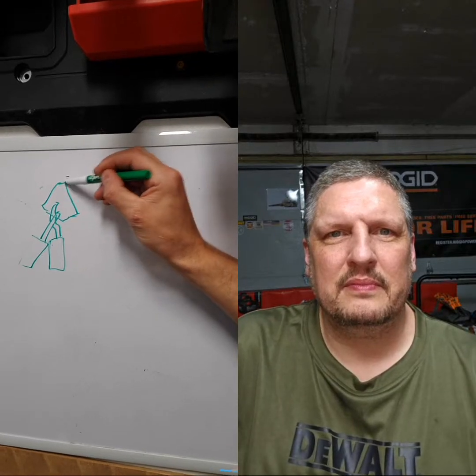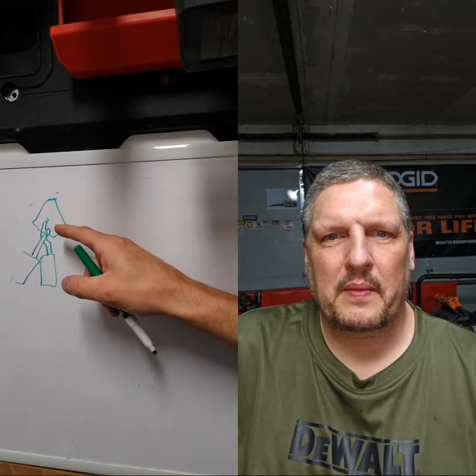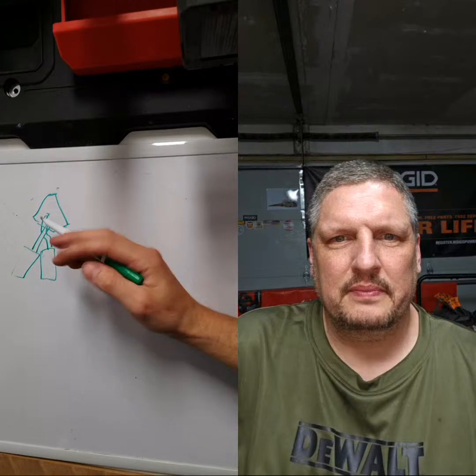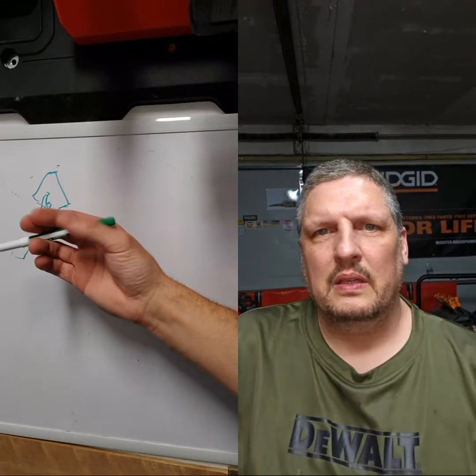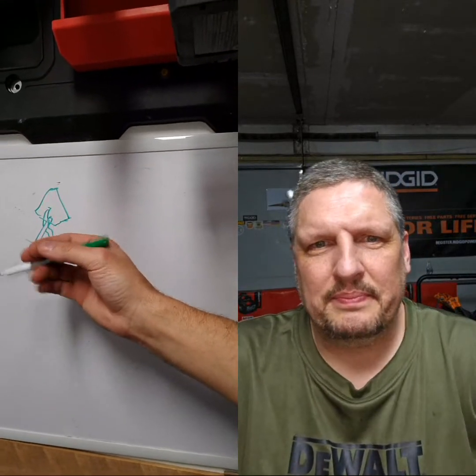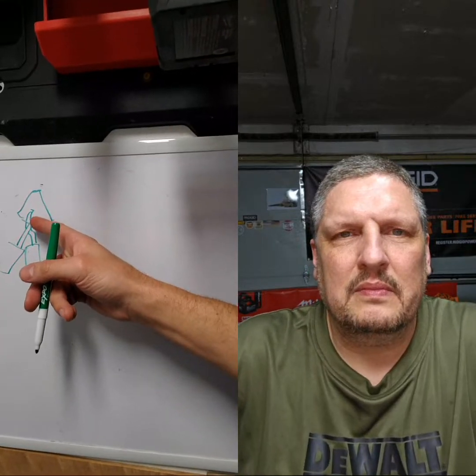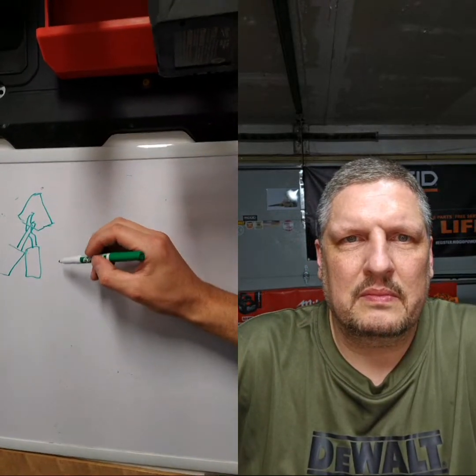Triangle. Wire nut's there, right? And we're not getting a good grab. And you got a little kind of popping arc. Moving away from that is not going to trip an arc fault. You know what's going to trip an arc fault? It's actually a constant arc.